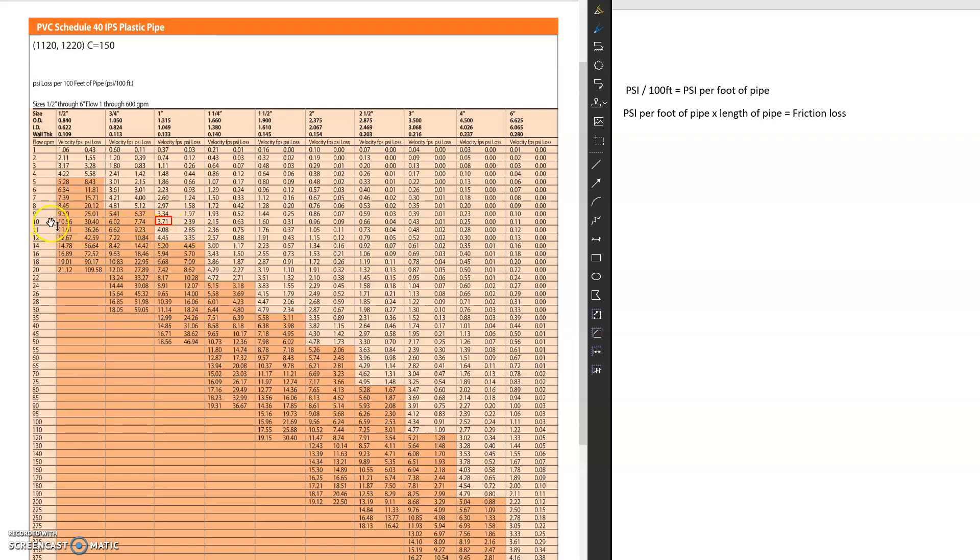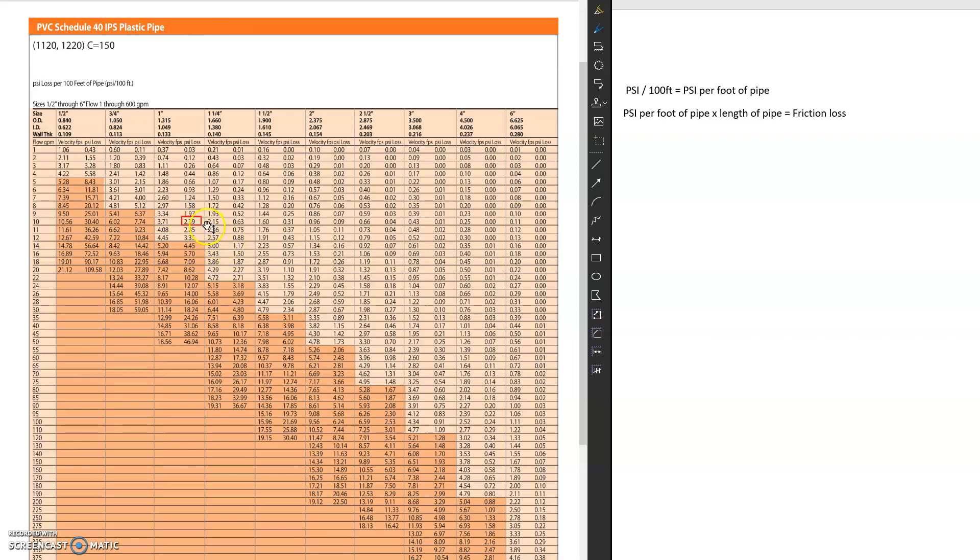So in this instance, 10 GPM, 1 inch pipe. Now we move over to the next column here and you're going to see that this is 2.39 PSI that we lose. But 2.39 PSI, what does that mean? Well, if you look up here, it says PSI loss per 100 feet of pipe. So for every 100 feet of 1 inch pipe, we lose 2.39 PSI.